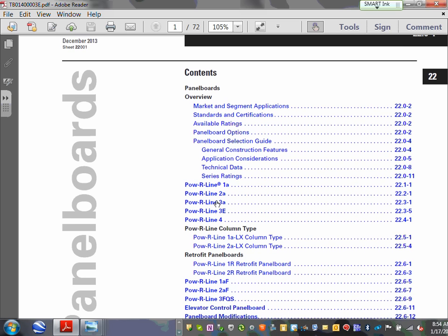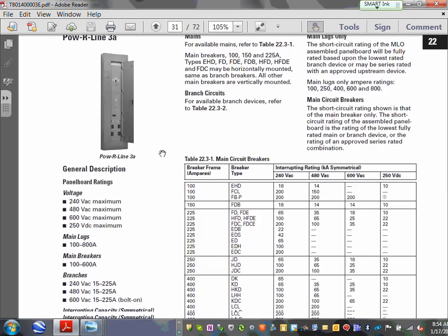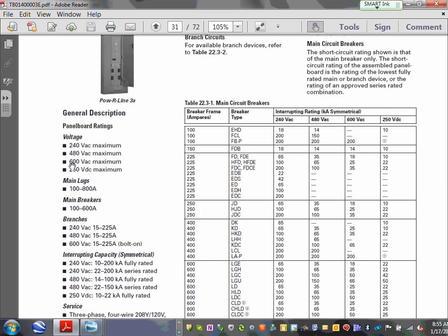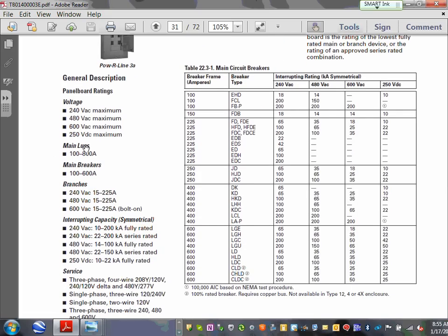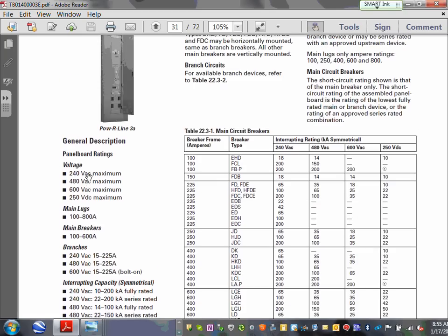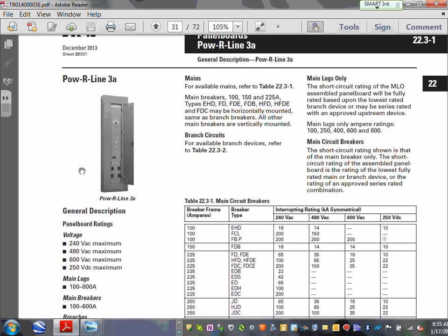If you go to the 3, look at that, getting bigger. Now I can go up to 600 amp, right? And look at the amps. The amps are lugs 800, max 600. Now this will be part of your mechanical panel. Your mechanical panel is going to be Pow-R-Line 3a because the amps went up. So I need a bigger panel. Does that make sense, guys?